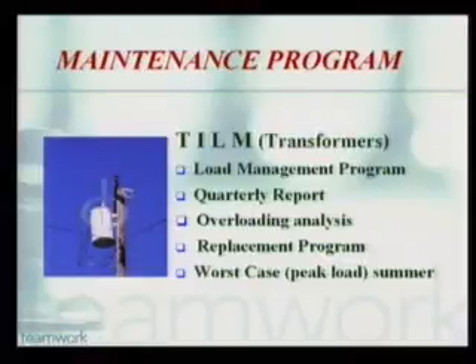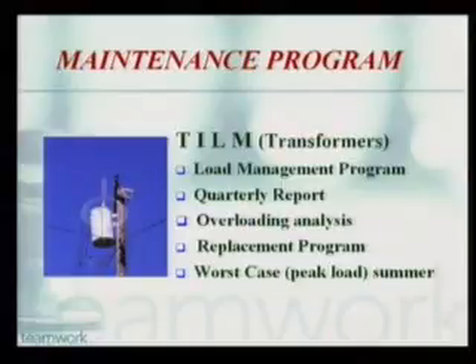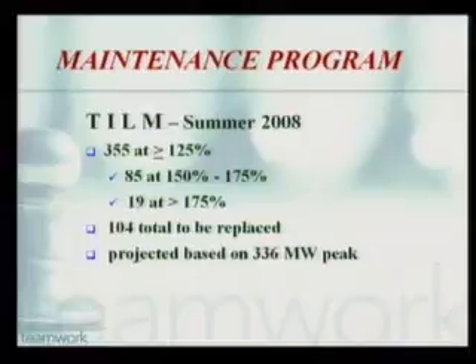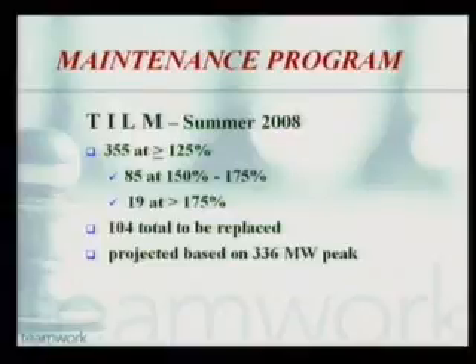We started this, and this will be our third year doing an active replacement before the summer. If you recall, the last 2 summers we barely had any problems with our transformers due to high loading. This year, based on the predicted peak and where the circuits will be, we estimate about 355 transformers will be loaded at about 125% or greater. What we want to focus on are transformers loaded at least 150% and higher, and replace them before the summer hits. This eliminates or prevents unnecessary outages due to transformer overloading. If you've been reading about the LA dilemma every summer on transformers, that's what we're trying to prevent here.